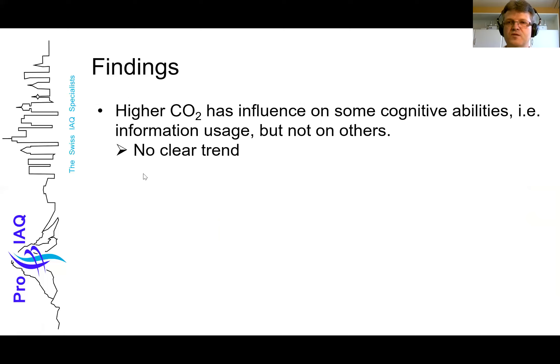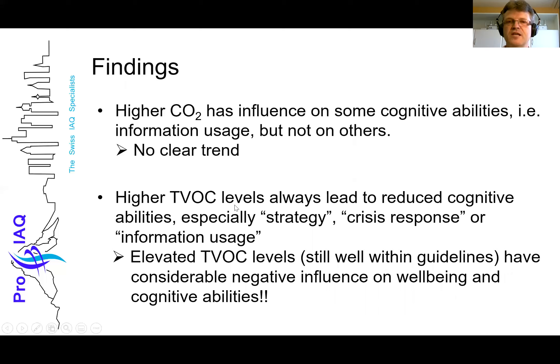The findings are that higher CO2 level has an influence on some abilities but not others — there's no clear trend. A welder in a welding bay can work at a maximum concentration of 5000 ppm for eight hours. It seems while our body is active, CO2 doesn't matter too much. However, at night to relax and refresh the body, we need lower CO2 content. Higher TVOC levels always lead to reduced cognitive function, especially strategy or crisis response — elevated TVOC levels, even within guidelines, have a considerable negative influence.